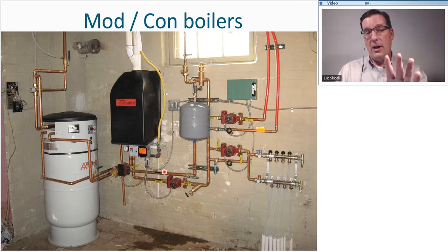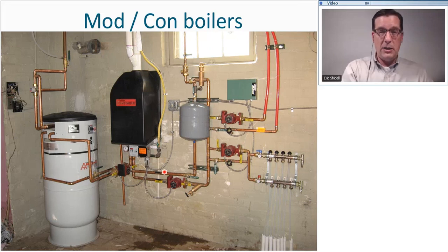To have a ModCon boiler hanging on the wall is pretty common. In fact, most of them are wall hanging applications. You can install a ModCon boiler on a stand so that it can sit on the ground, but you'll have to order that stand separately. It's an accessory, or build it yourself. ModCon boilers, by and large, are designed to mount on the wall. There are a small handful of large commercial size modulating condensing boilers that sit on the floor, but they're going to be greater than 400,000 BTU per hour. So anything under 400,000 BTU per hour is generally going to be wall mounted.